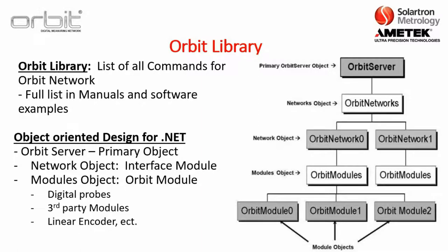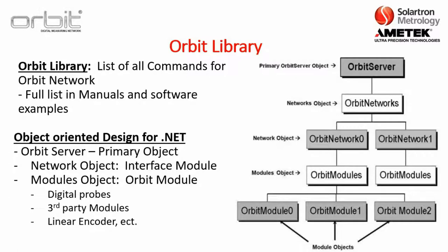And that's where, so, the Orbit server, it's a primary object for it. And then you have a network object, which is typically an interface module, such as the USB interface. And then you have the modules object, which is just an Orbit module. So, an Orbit module would be digital probes, third-party modules, or the linear encoder. So, basically, each object has a set of functions or methods that are used to initiate specific actions and a set of parameters or properties that can be read or set.